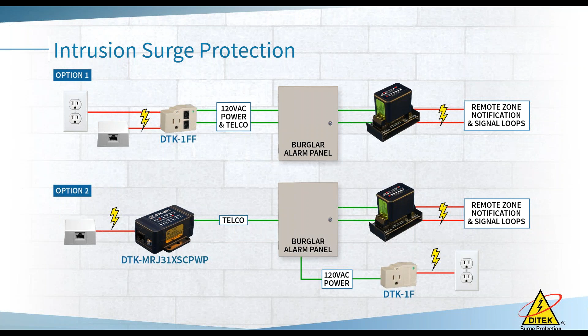The other thing we're concerned with is 12-volt remote zones, whatever those might be. It could be a pole barn with a motion sensor out there, or a portable classroom with a motion sensor. Maybe you're not concerned with the motion sensor itself, but you definitely don't want that incoming wire or barrier coming back into your burglar panel and cooking it. So for those remote zones, you definitely want to stop surges from coming back into the panel.